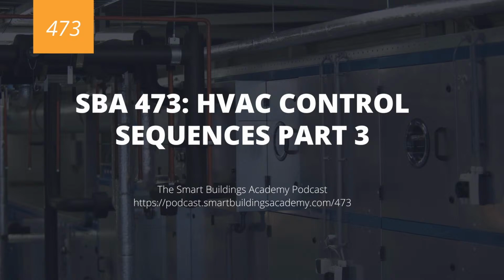Which once again, we're going to talk about in just a second. There's a lot in this episode. Okay, so let's take a look at the sequence. So the sequence right here, temperature sensor will determine if the unit is in heating, cooling, or ventilation mode during occupied operation. I told you this episode might be a little wonky as I get back in the swing of things.